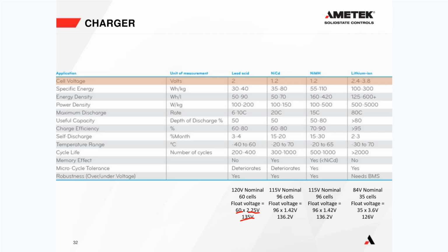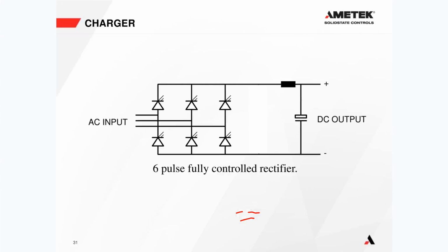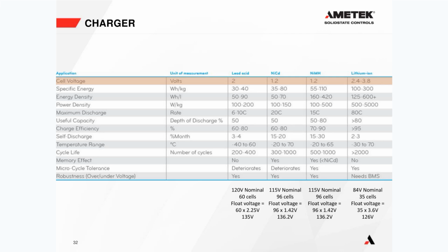So that is exactly what the battery charger does. If we go back to the previous slide, when you measure positive to negative here for a 60 cell lead acid battery, you're going to have 135 volts DC. That is why it's only dictated by the battery. We don't make it 135 volts because that's what the inverter needs, absolutely not, it's because that's what the battery needs. It's the only reason we set the voltage at that level.